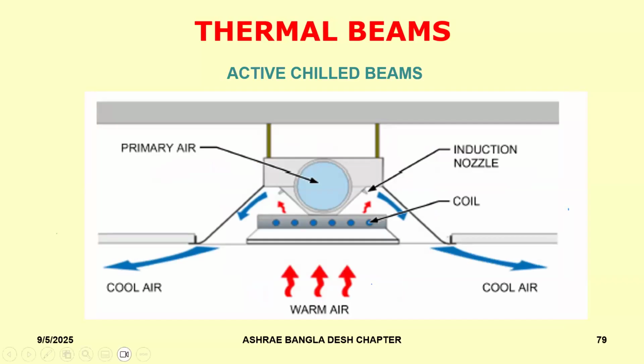So what do we do here? We have the same coil, which is taking care of the room sensible load, and we use a duct to bring in the outside air, which is treated to take care of the breathing zone air. And that is admitted into this chamber through specially designed nozzles. Now, as the air exits this nozzle at a high velocity, it creates an area of low pressure behind the coil. And that area of low pressure will tend to draw the warm air from the room into the coil. It comes, gets cooled, mixes with this air, and then leaves in a Coanda effect, and this mixes with the room air properly and then keeps everybody comfortable.